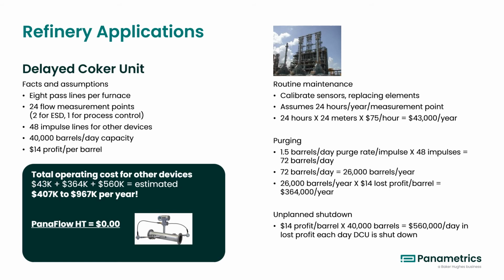Purging is required on the lines for a non-ultrasonic flow meter. For a 1.5 barrels per day purge rate with 48 impulse line equates to 72 barrels per day. 72 barrels per day is 26,000 barrels per year. With 26,000 barrels per year and a $14 loss profit per barrel, it equates to $364,000 per year.